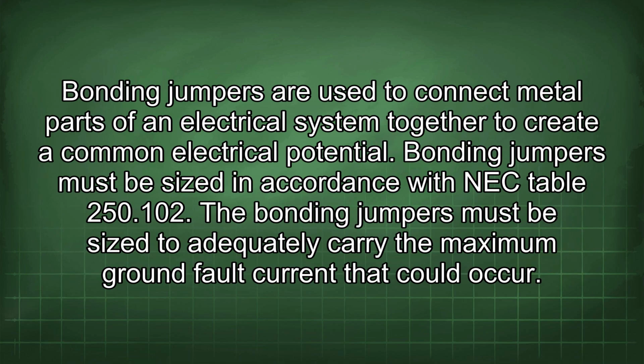Bonding jumpers are used to connect metal parts of an electrical system together to create a common electrical potential. Bonding jumpers must be sized in accordance with NEC Table 250.102. The bonding jumpers must be sized to adequately carry the maximum ground fault current that could occur.